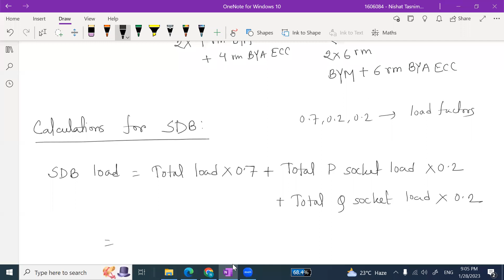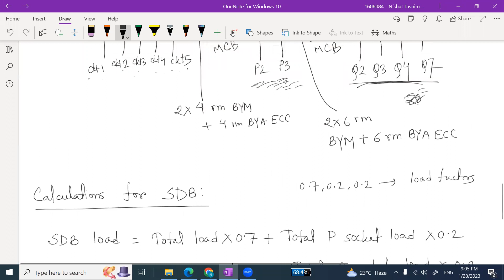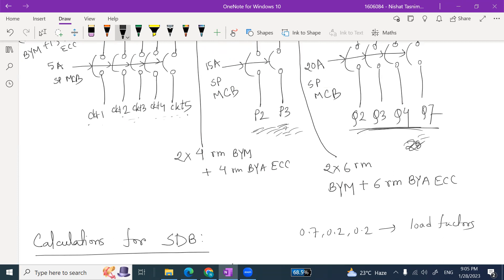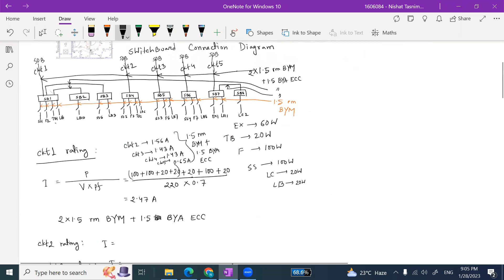Total P socket load, and let's assume this 0.2, and total Q socket load, and let's assume we only use this load 20% of the time, 0.2. So 0.7, 0.2, 0.2, these are load factors, like an activity factor. Okay, so we need to calculate the total load. The total load is basically circuit 1 load, circuit 2 load, plus circuit 3 load, circuit 4 load, circuit 5 load. Now we need to go back here. So can you tell me what is the total load?